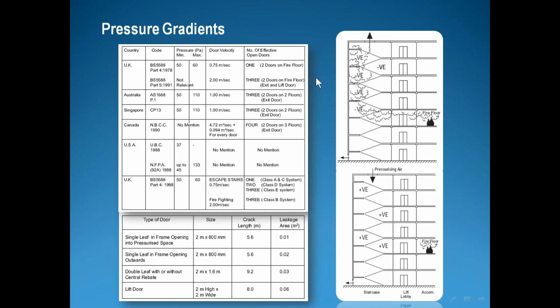Here, in most common codes, they state that we have to make a pressurization system inside the stairs and in the elevator shaft to protect these egress routes from any penetration of the fire and the smoke. This is why we consume some minutes in this presentation on the door, because it is an important issue. If you have a very good separation between the affected zone and the stairs, you can be assured that the people's travel time from the source of fire till here will be a minimum. If they get inside this, they are in a protected zone.